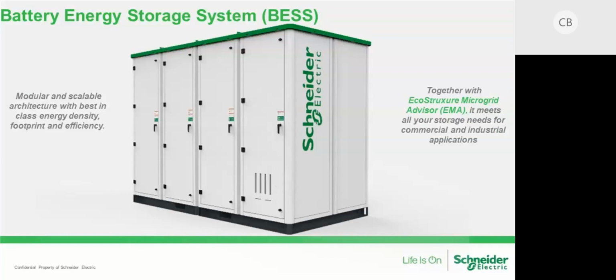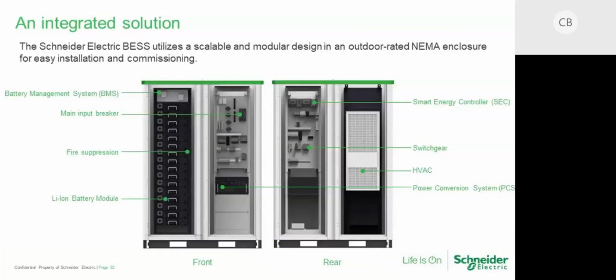These are NEMA 3 and 4 rated, so they can sit outside. They have all the battery management system inside in order to smartly charge and discharge the batteries. It has full fire suppression inside and meets all the codes and requirements right now. It includes HVAC control, all the switchgear, and the controller, because a system needs to be told when to charge and when to discharge. So that's part of how we interface with this smart energy controller. And then all the power conversion systems are also included in there.